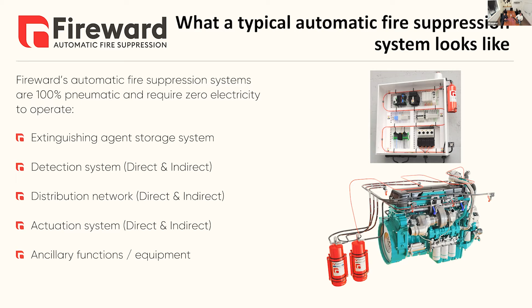And the shutdown, as Ed said, is important on machinery to stop the flow of any diesel or hydraulic oil that has caused the fire in the first place. As probably some of you have experienced on plant and equipment, a large number of the fires are electrical fires, and the system, when it detects a fire, isolates the batteries and any electrical source onto the asset that we're protecting. So if an electrical fire does start, it means that we're isolating any more current from going into the fault that then has caused the electrical fire in the first place. So there's some really clever add-ons that we have with the system.